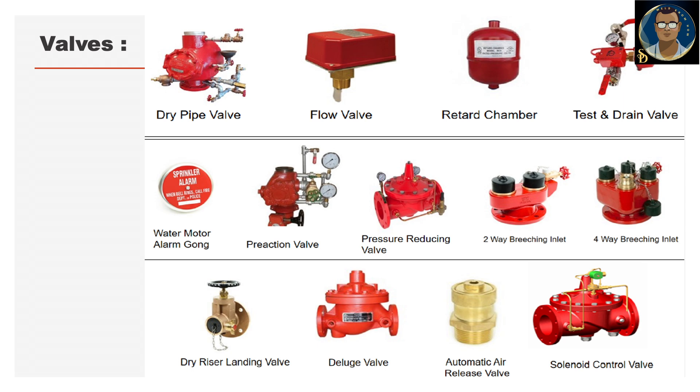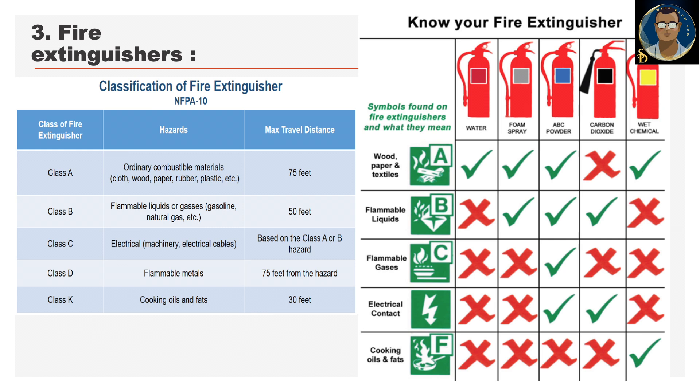Fire extinguishers are portable devices that allow occupants to suppress small fires quickly. Primary types and their applications: water extinguishers are suitable for Class A fires involving ordinary combustibles like wood, paper or cloth. Dry chemical extinguishers are effective for Class A, B and C fires — very extensively used — involving flammable liquids, gases and electrical equipment. CO2 extinguishers are ideal for Class B and C fires as they displace oxygen and extinguish fire without leaving residue. Foam extinguishers are suitable for Class A and B fires, as the foam creates a barrier between fuel and oxygen.